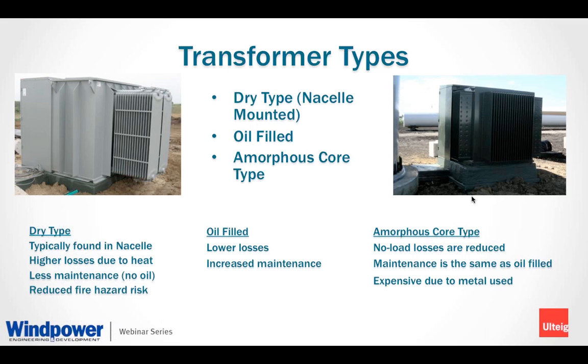Another type of transformer is the amorphous core type transformer. This particular transformer has a very unique metal that's used in the transformer, which decreases the no-load losses. They tend to be a lot more expensive, but if you think about a wind farm, it's not windy all the time. Half the time the wind is not blowing, these transformers are actually being energized by the system and having losses built up on them. So the amorphous core transformer decreases that tremendously.